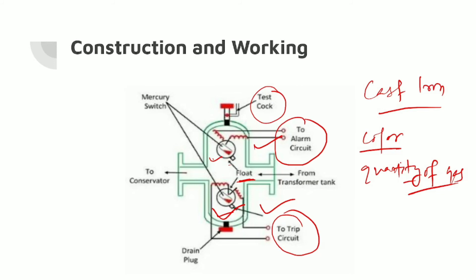There is a provision for operating the trip and alarm mechanism manually — you can activate the trip and alarm circuit manually. To pump air through the pet cock and operate the relay is one of the simple methods for testing the working of the relay. You can manually use the test cock, provide the gas, and see if the alarm circuit and trip circuit are working.